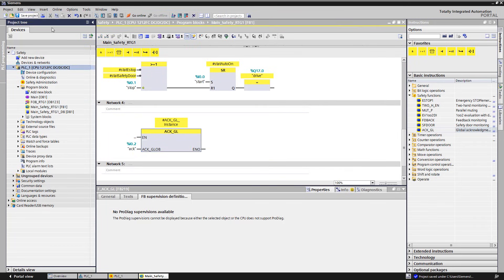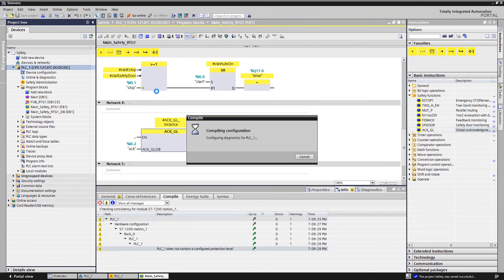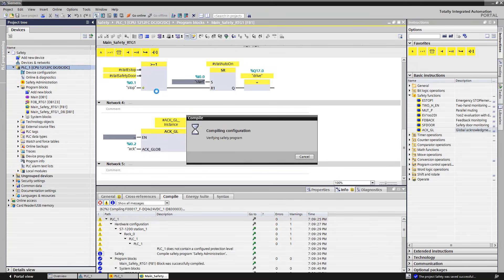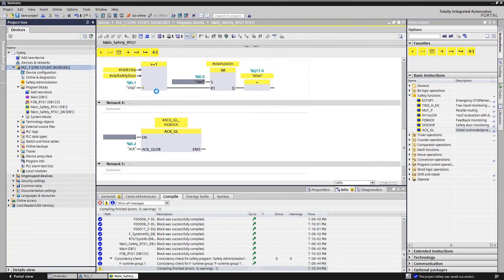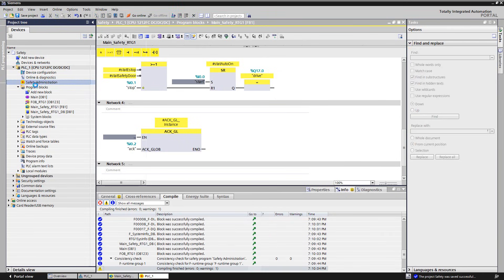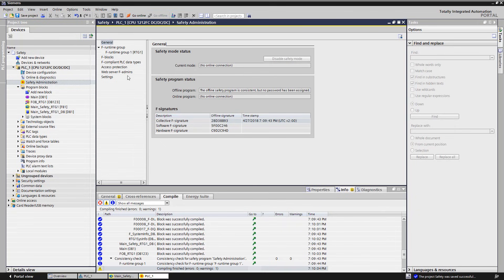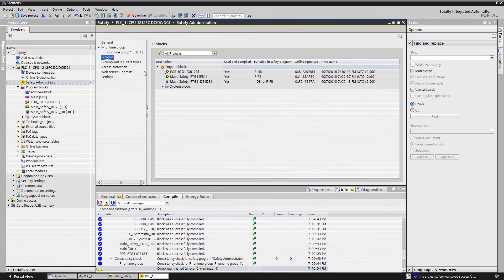We compile the safety program and the entire project. After the compile, we see in the safety administration editor the listing of the offline signatures. The signatures are unique and relevant for the safety-related acceptance of the plant. The signature changes if a modification is made to the implemented hardware or to the safety program. The signature is also generated module granular.